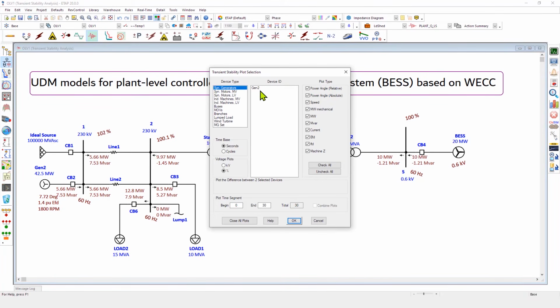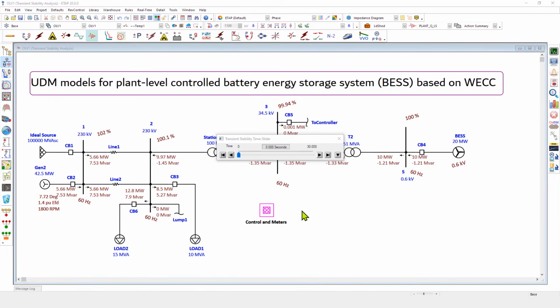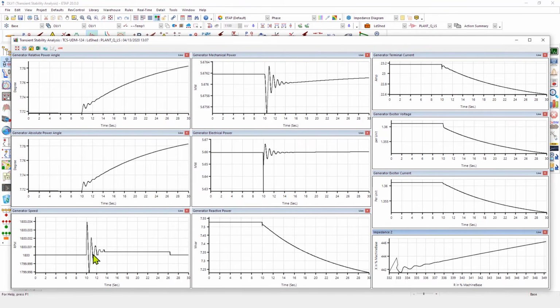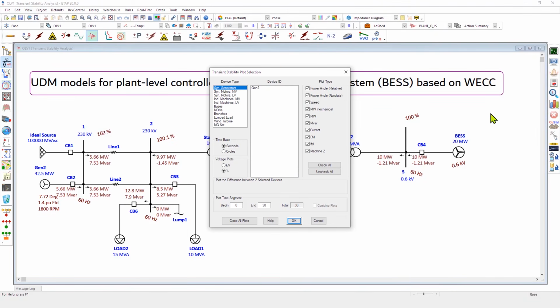You can also use the plot view to observe plots for various other components in the system, such as the generator, and observe all the different parameters of the unit as it goes through this disturbance. And you can see that the relative angle change is very minimal and the generator speed fluctuation is also very minimal, but nonetheless you can see in detail the transient nature of the change in generator speed as that load is dropped, and then the compensation is provided by the battery energy storage system. Depending upon the controller, you can set up the battery to either discharge, charge, or automatically charge and discharge. And this is purely a function of the control system itself.